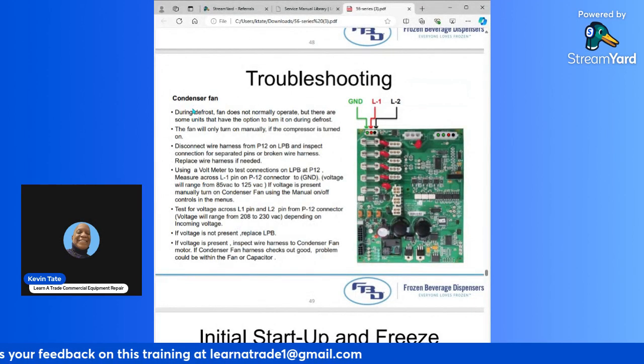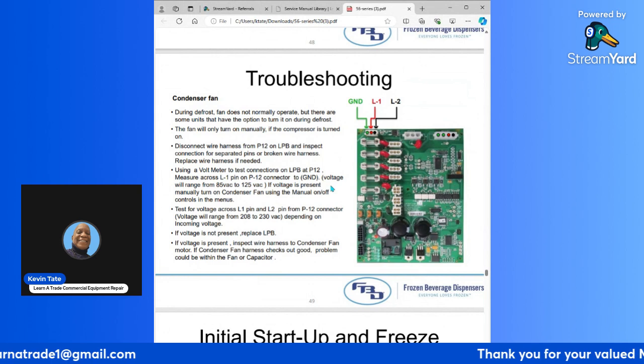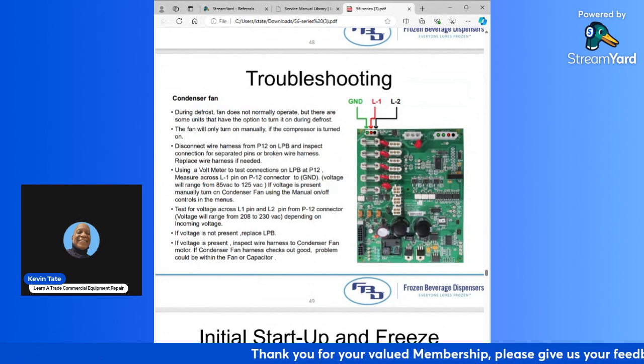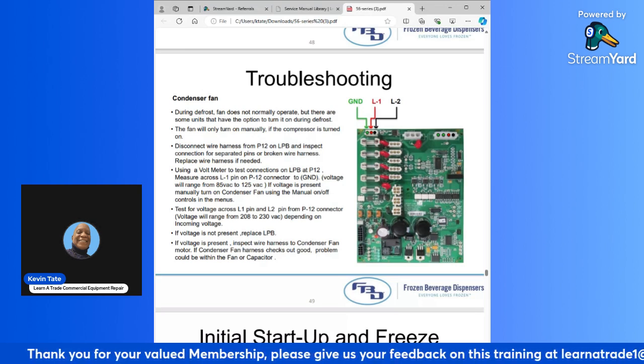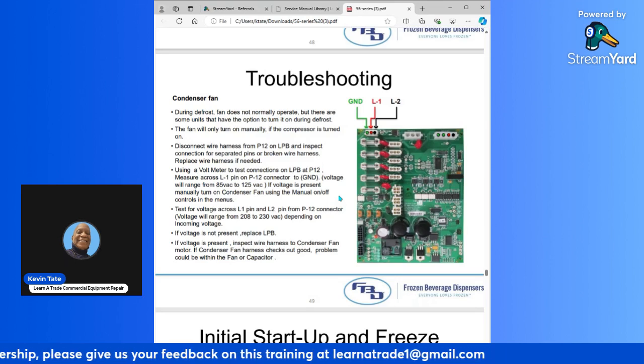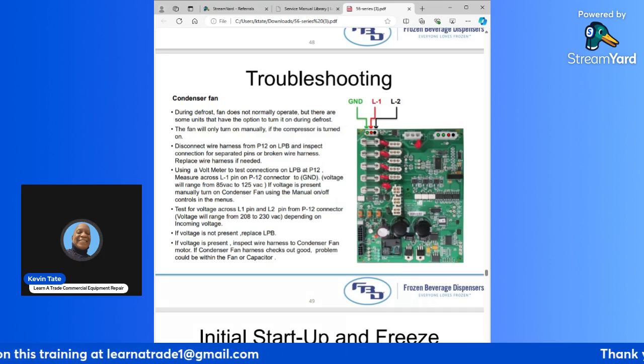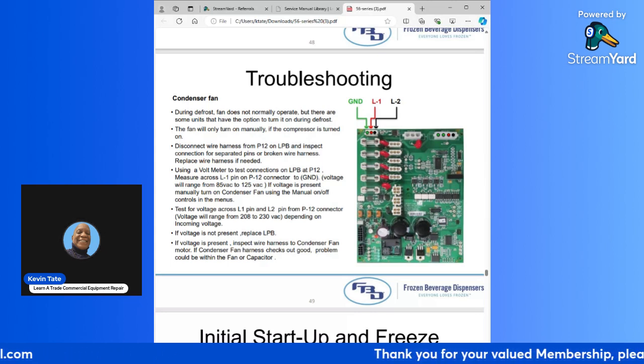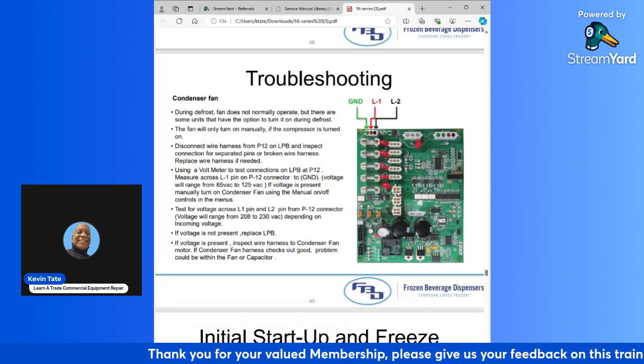Troubleshooting, condenser fan. During defrost, the fan does not normally operate, but there are some units that have the option to turn it on during defrost. The fan will only turn on manually. If the compressor is turned on, the fan should come on.